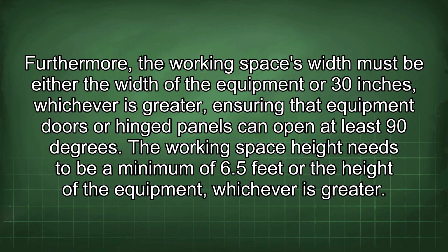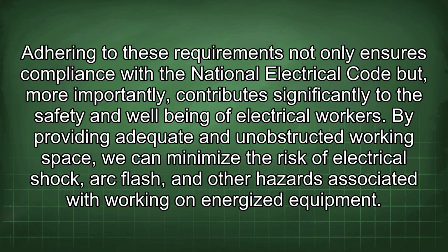Furthermore, the working space's width must be either the width of the equipment or 30 inches, whichever is greater, ensuring that equipment doors or hinged panels can open at least 90 degrees. The working space height needs to be a minimum of 6.5 feet or the height of the equipment, whichever is greater.